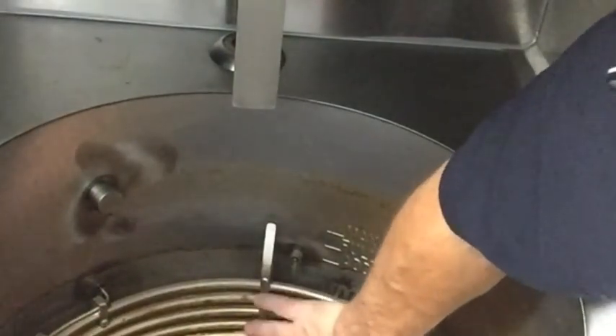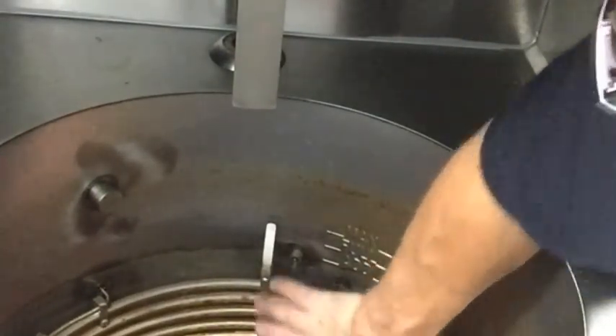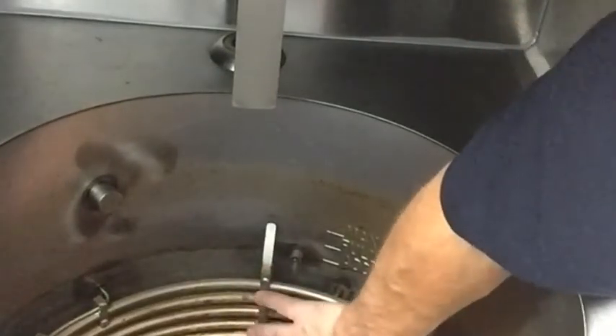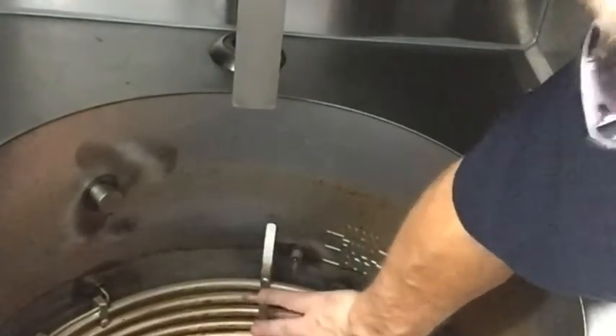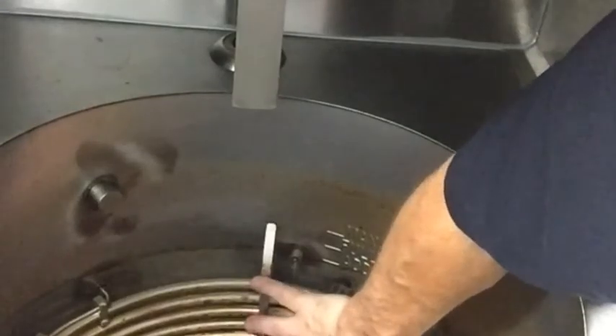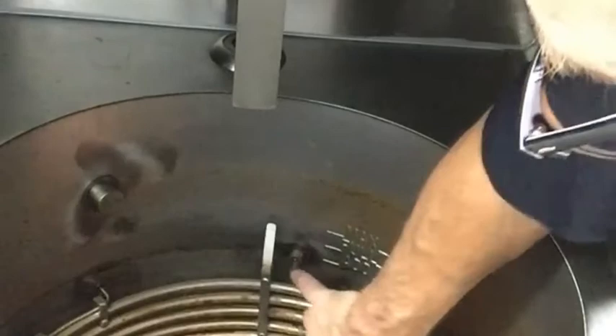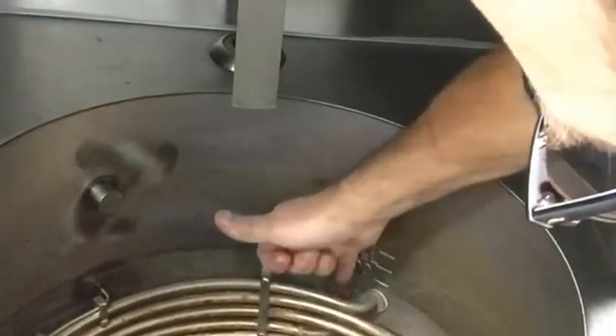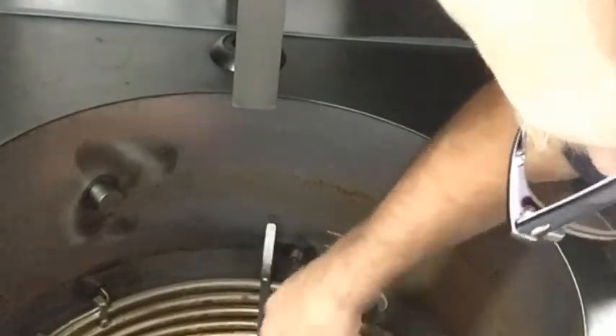Expansion and contraction as it heats and cools will sometimes loosen up these screws. So a good preventive maintenance thing is to come through and just make sure these are tight whenever you come in and the oil is down. Go ahead and snug them up. Again, element probe, you'll see it's right against the element, tightened up nice and tight against the element. Your oil level probe, your high limit probe, and below that your variable probe.